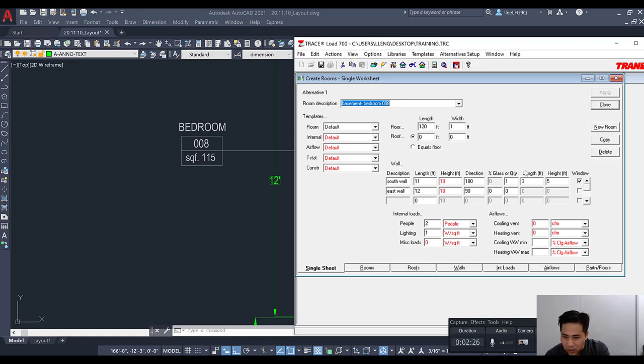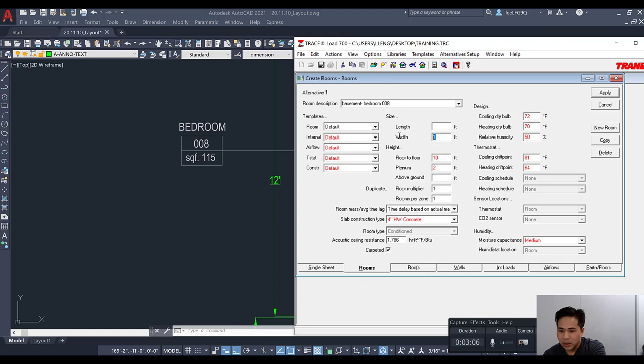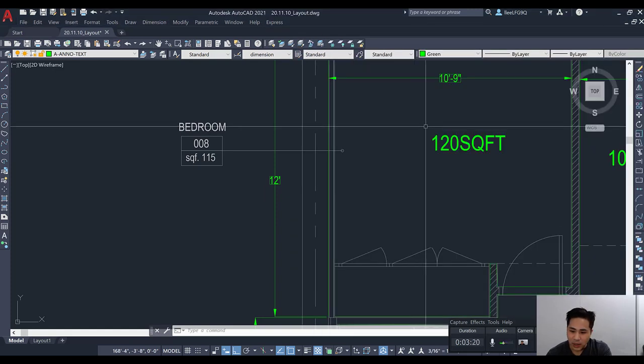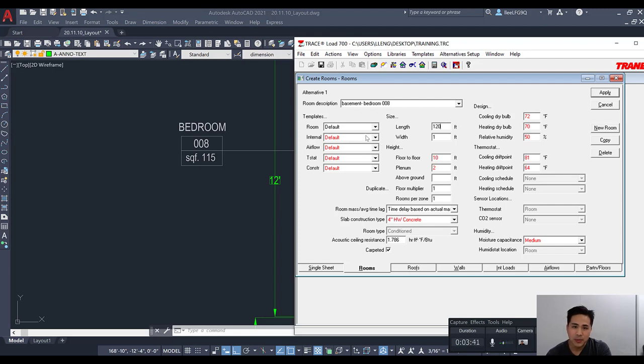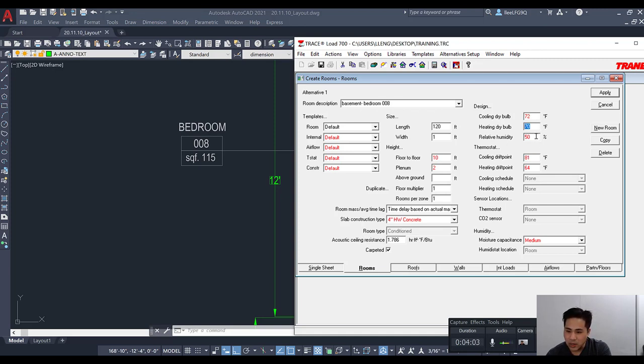I'm going to start with the room tab. The data you put into the length and width just has to multiply to equal the square footage of the space. The simplest way is to make one value 1 and the other the square footage — so here it's 120 square feet, making it 1 by 120. The values shown in red represent those coming from the template we just created, such as floor-to-floor of 10, plenum of 2, cooling at 72, heating at 70, and relative humidity at 50%.